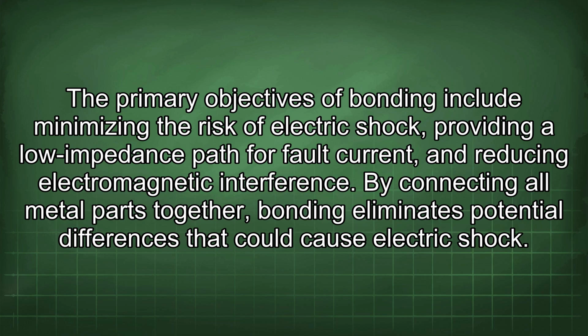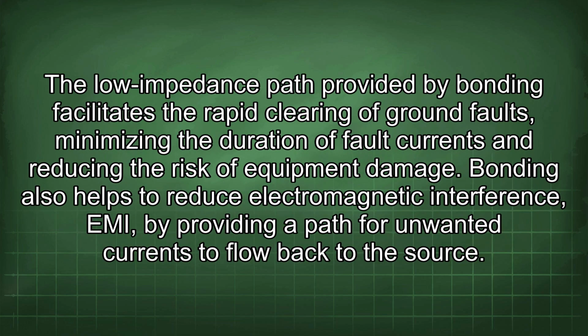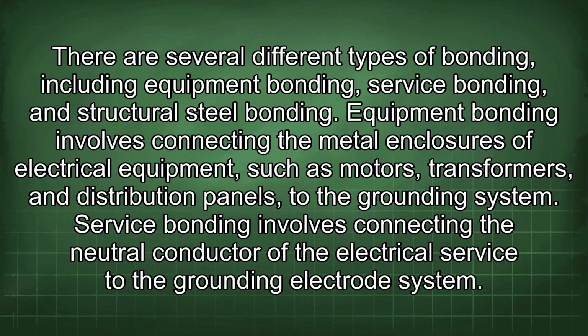and reducing electromagnetic interference. By connecting all metal parts together, bonding eliminates potential differences that could cause electric shock. The low impedance path provided by bonding facilitates the rapid clearing of ground faults, minimizing the duration of fault currents and reducing the risk of equipment damage. Bonding also helps to reduce electromagnetic interference, EMI, by providing a path for unwanted currents to flow back to the source. There are several different types of bonding, including equipment bonding, service bonding, and structural steel bonding.